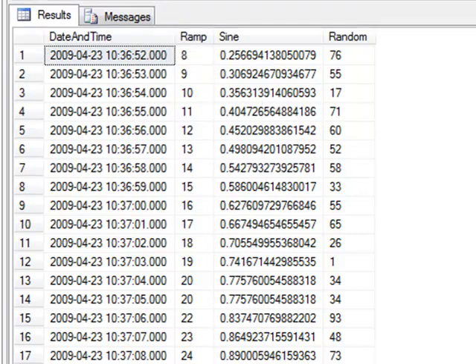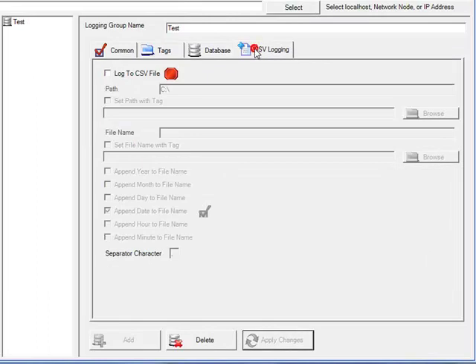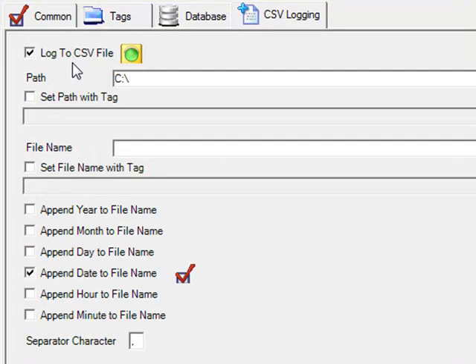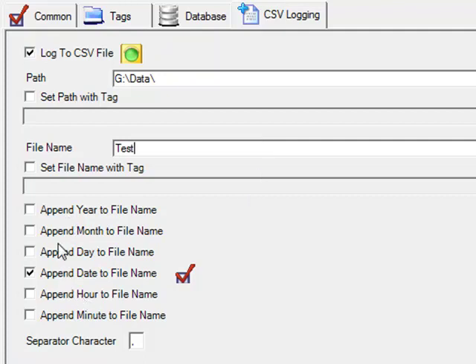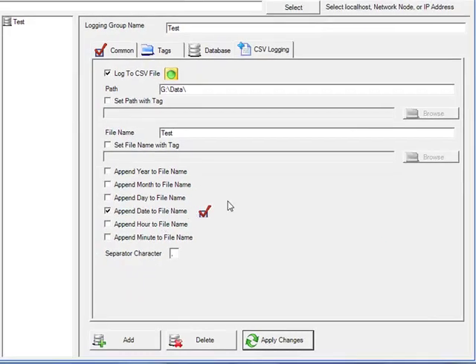Now, let's see how we would log to a CSV file. Let's go back to configure data logging, and under the CSV logging tab, we will enable log to CSV property. So I can now specify the path as g colon backslash data backslash, which is the directory that I want to log my files to. Let's enter a file name of test. And here we can optionally append on to the year, month, day, or the default is to append on year, month, and day so that each day a new file is automatically created. We can also append on an hour and a minute onto each file name.